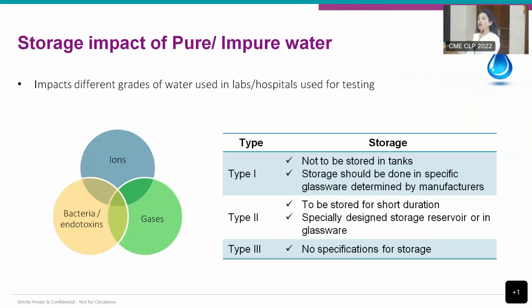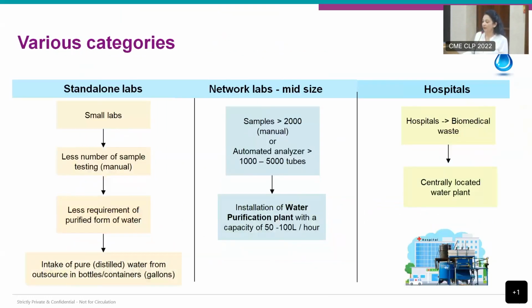So type 2 water is what we are dealing with. उसको short duration के लिए store कर सकते हैं. Short duration every lab has to devise. Ideally 4-5 days से ज़्यादा नहीं चलता है. और फिर specially designed storage reservoir होना चाहिए, which needs to be cleaned periodically. That's it. Type 1 is an ultra pure water. उसके जो बहुत strict conditions हैं, there is a special storage tank जो बना है. And type 3 is non-specific. We know that it's used majorly for autoclave and washing, right?